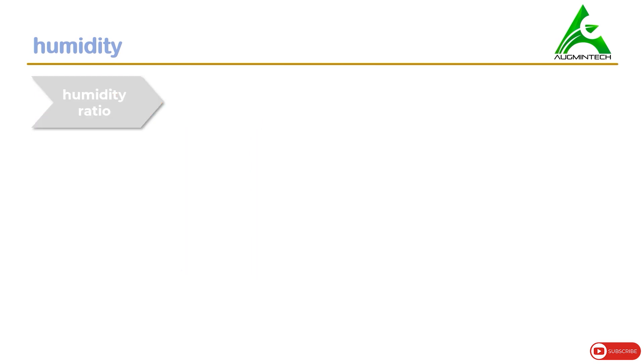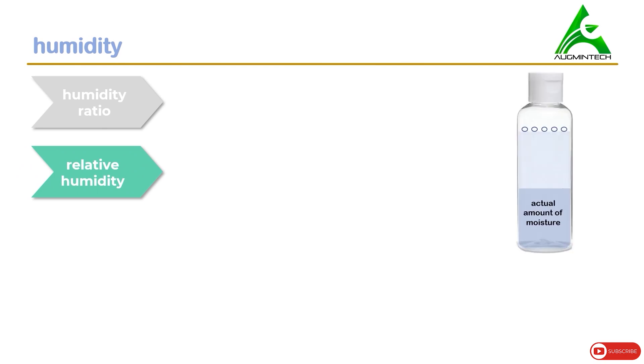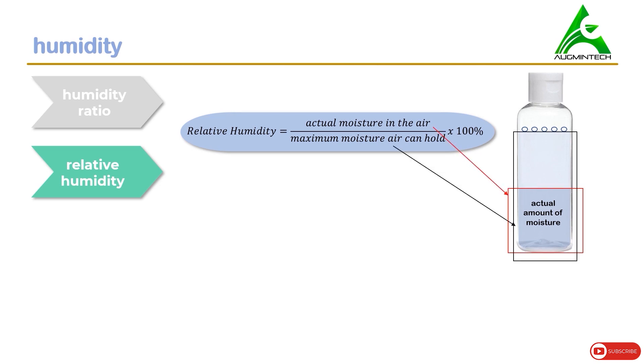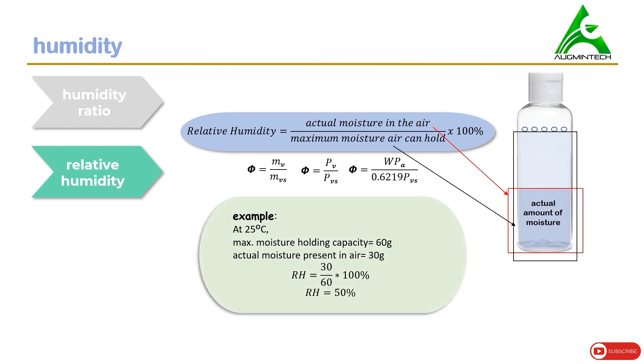Relative humidity is the ratio of actual moisture in the air to the maximum moisture the air can hold, multiplied by 100%. Unlike humidity ratio, relative humidity is related to the maximum amount of water vapor the air can hold. Relative humidity is represented by φ, so φ = MV / MVs, where MV is the mass of actual water vapor and MVs is the mass of maximum water vapor the air can hold. This can also be written as pressure ratios.